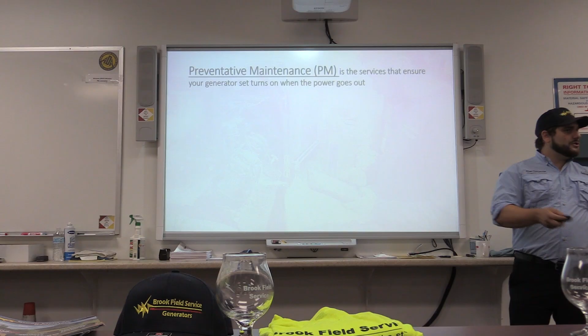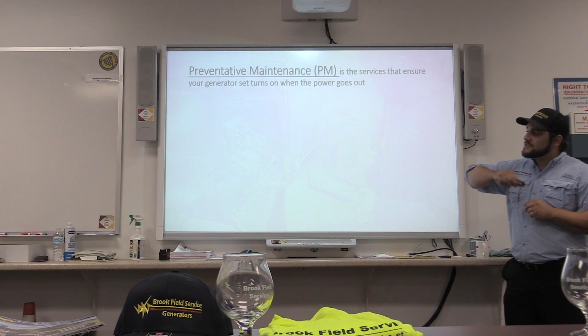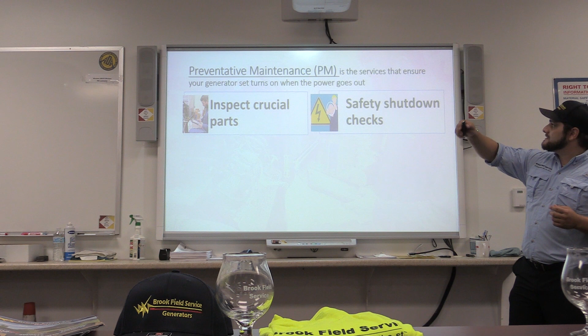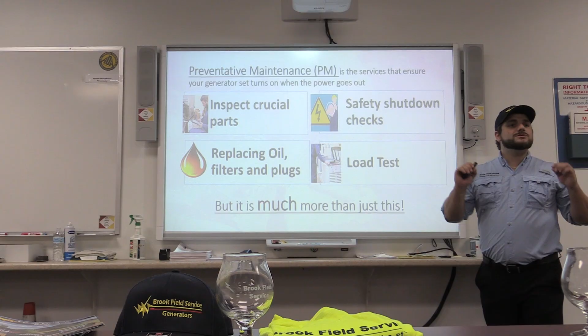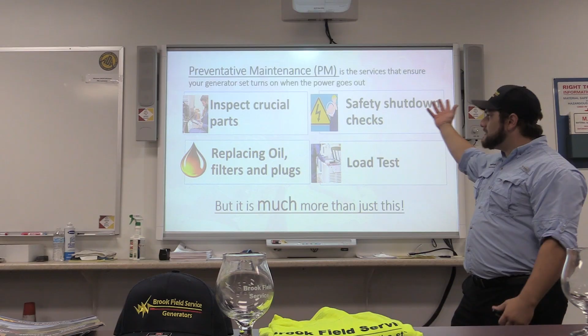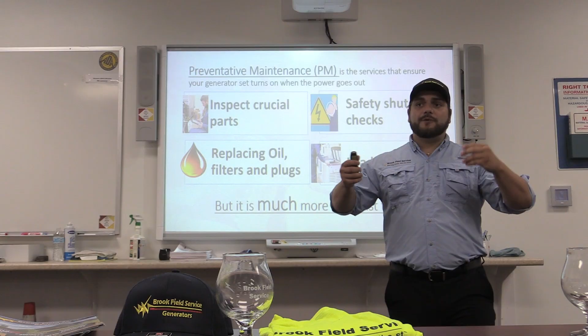Jumping into the generator maintenance side of things, preventative maintenance is the term for the services that ensure your generator set turns on when the power goes out. That includes everything from inspecting crucial parts, safety shutdown checks, replacing oil filters and plugs, and load tests. But it's so much more than that. I know a lot of guys have their own maintenance team that handles replacing oil filters and plugs and inspects some things, but there are things that you need a licensed technician for, both for the generator and for the transfer switch.